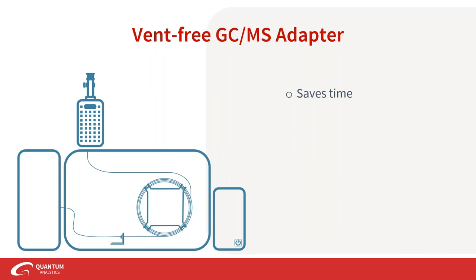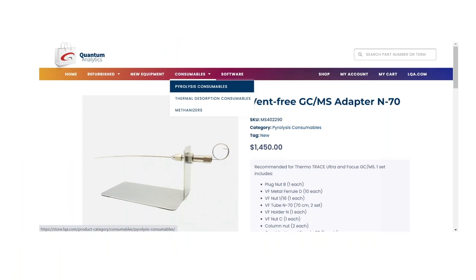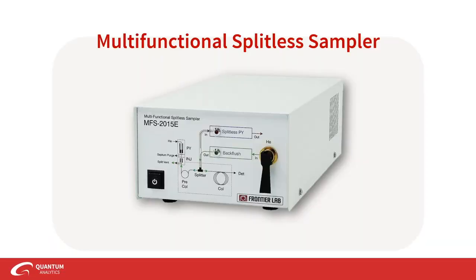The VFA allows easy switching between columns — whether switching from an EGA column to a regular separation column, or trying a polar versus non-polar column based on your analytes. The VFA can be used with or without a pyrolyzer. It's just a line you can install yourself, priced at the level of consumable items you'd budget for your lab anyway, and available on our online store. It makes a lot of sense to have the VFA on any GC-MS.